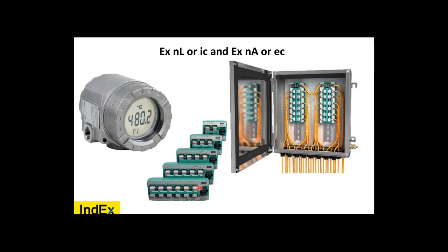But when it's outside, in a hazardous area, zone 2 or anywhere, it has to be inside of an enclosure. So then you had them inside EXNA. Then as the standard updated in 2017 from edition 4 to edition 5, NA becomes EC. So now the IC goes inside the EC, which feeds the IC instrument.